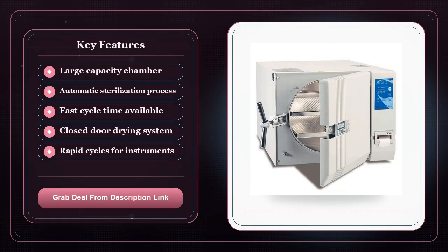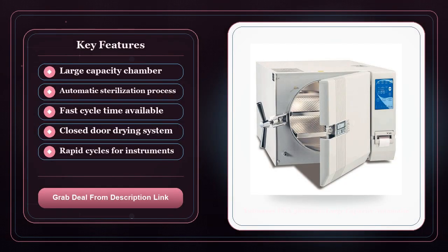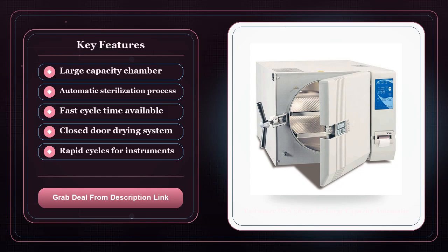On the flip side, if you're a solo practitioner, a boutique spa, or a small podiatry office that only needs to sterilize a few trays a day, the 22-gallon chamber can feel like overkill. The footprint of the unit is sizable. You'll need a dedicated space with proper ventilation and a stable power supply. It's not a piece you can tuck under a counter. The larger the machine, the more it draws on your electricity bill. And while the power draw isn't astronomical, it's something to factor into your operating budget if you're already watching overheads.